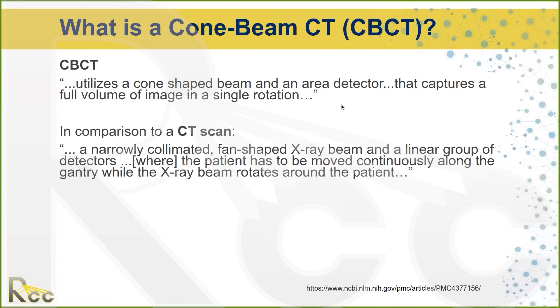What's different about a cone beam CT from a regular CT scanner is that it uses the whole x-ray beam with a flat square or rectangular shaped panel. In a CT scanner, the collimation on the detectors is really tight — only a little tiny slit is let through. So even though it's still sort of a cone beam in a regular CT, the detectors are only letting a small slit through.